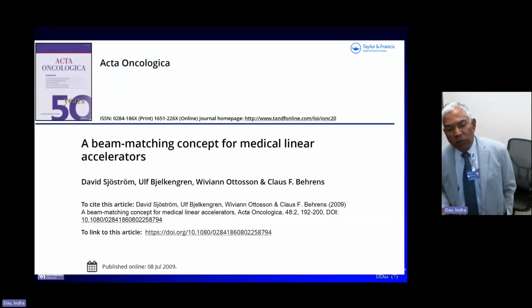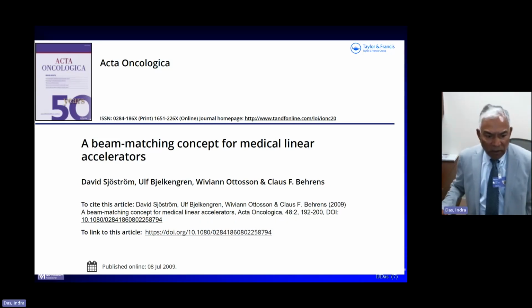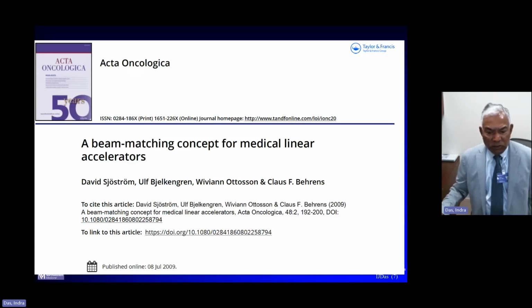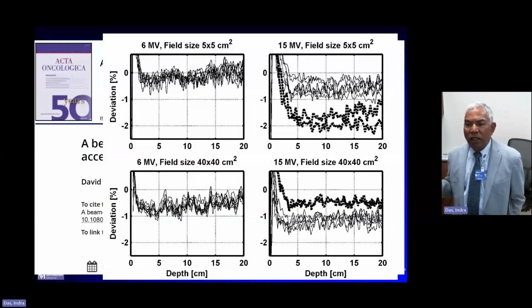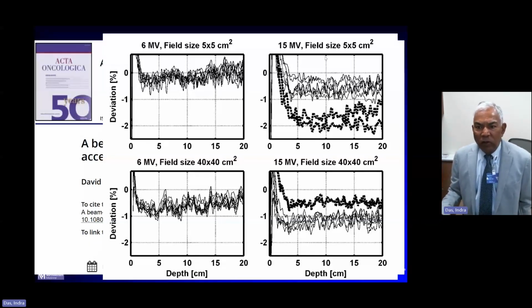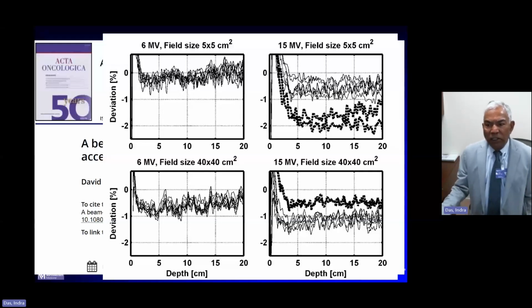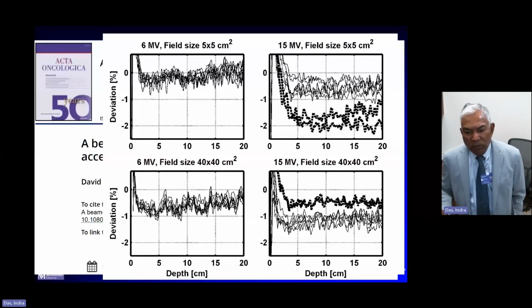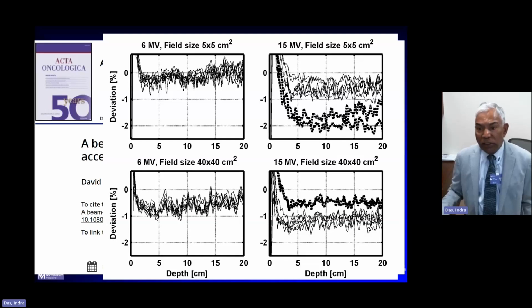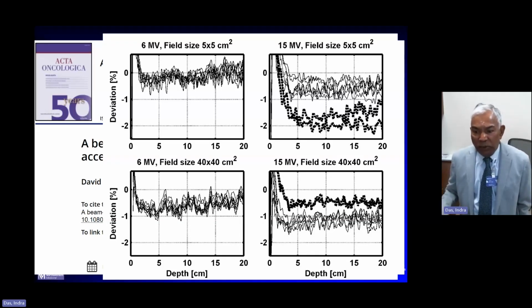What happens when people take data? This is data from Sweden, and they compared 9 machines from one institution. Obviously, these are of different vintage, and they compared all kinds of parameters. So looking at the small fields, the low energy, high energies, large fields, and again high energy. You can see here that the data of the 9 machines are split into two sets, one here and the other one here. Obviously, these are the percent deviations, -2% and -1%. And obviously, at beam commissioning time, these become -1 or -2%. I think this becomes significant. And we'll come back to what your criteria should be.